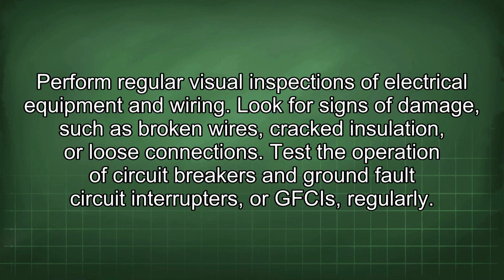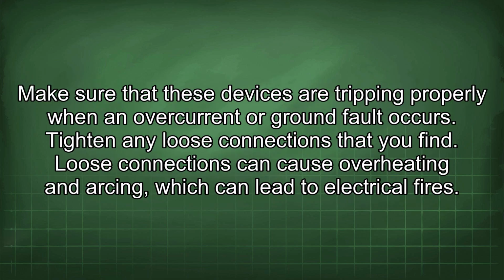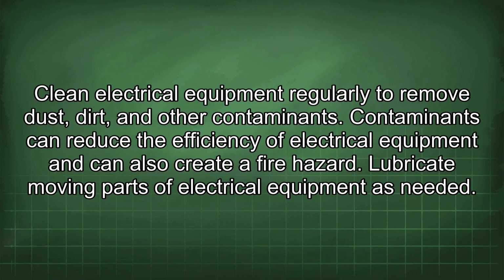Test the operation of circuit breakers and ground fault circuit interrupters, or GFCIs, regularly. Make sure that these devices are tripping properly when an overcurrent or ground fault occurs. Tighten any loose connections that you find. Loose connections can cause overheating and arcing, which can lead to electrical fires. Clean electrical equipment regularly to remove dust, dirt, and other contaminants. Contaminants can reduce the efficiency of electrical equipment and can also create a fire hazard.